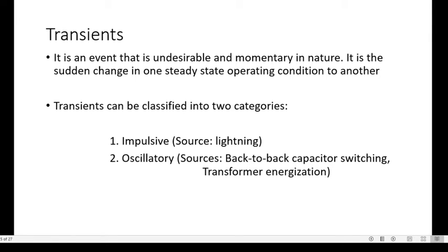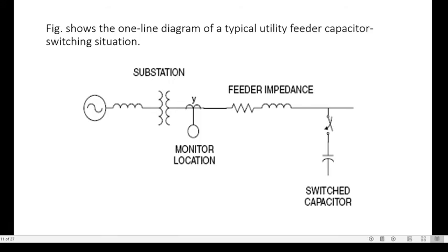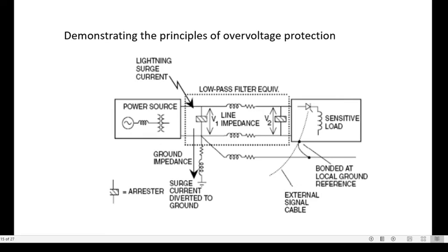So we have discussed these isolation transformers. Then low pass filters are basically used. As I told you, this is the low pass filter. Let me show you. The position of the low pass filter. It is to achieve better protection for higher frequency transients. The low pass filters are composed of series inductors and parallel capacitors. This LC combination provides a low impedance path to ground for selected resonant frequencies.